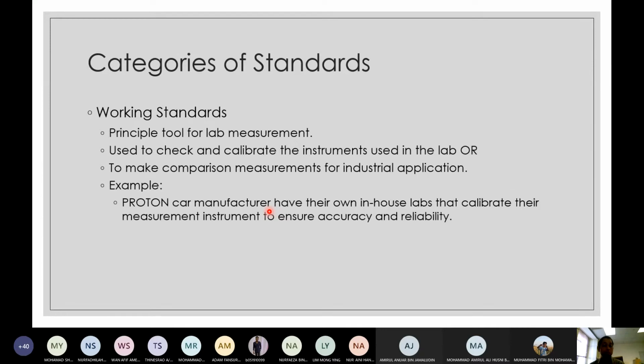And finally, we have the working standards. Working standards are the principal tool for lab measurement, used to check and calibrate instruments or make comparison measurements. These are available in every factory, processing plant, or company involved in measurement. For example, Proton, the car manufacturer, has its own in-house laboratories that calibrate its measurement instruments to ensure accuracy and reliability.